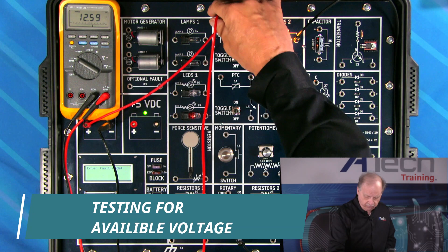So the first thing I want to do is come over before my circuit breaker. I've got 12.59 volts, so interestingly, 12.59 here and 12.59 here — there is no resistance in this wire, so there's no voltage drop across the wire. Now I'll go to my switch up here, and you'll notice I have 12.45 volts.